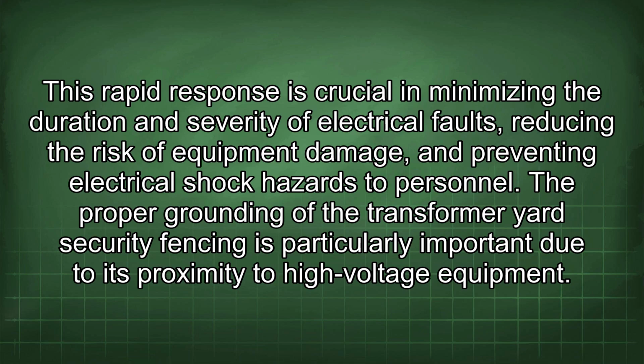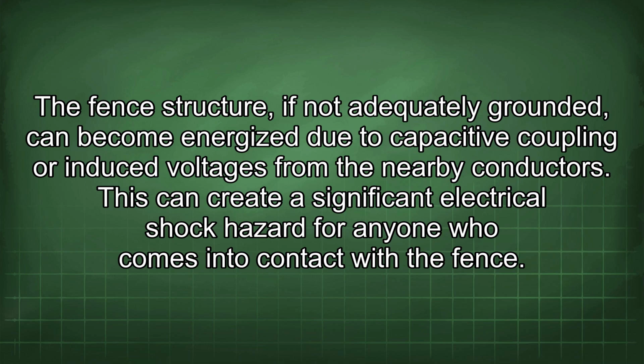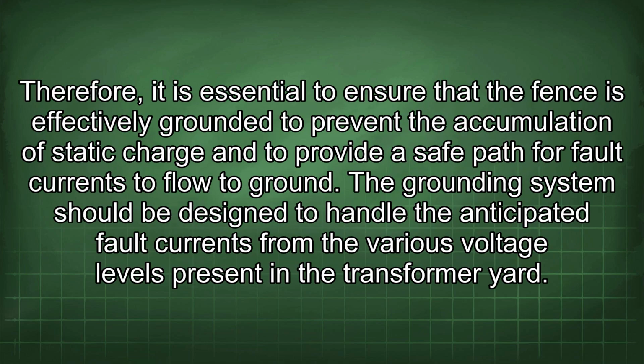The proper grounding of the transformer yard security fencing is particularly important due to its proximity to high-voltage equipment. The fence structure, if not adequately grounded, can become energized due to capacitive coupling or induced voltages from the nearby conductors. This can create a significant electrical shock hazard for anyone who comes into contact with the fence. Therefore, it is essential to ensure that the fence is effectively grounded to prevent the accumulation of static charge and to provide a safe path for fault currents to flow to ground.